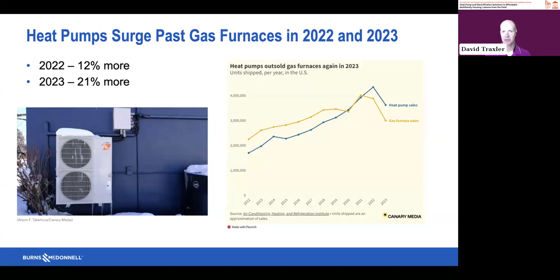So when you're designing a building to be fully electrified, you have to do it differently than you did past buildings. Traditionally, you had a gas furnace that you would size for the heating load, and you had the air conditioning portion and condenser unit you would size for the cooling load. But when you electrify your building, a single unit provides both your heating and cooling, and that can vary significantly throughout the United States, depending on where your building is located.